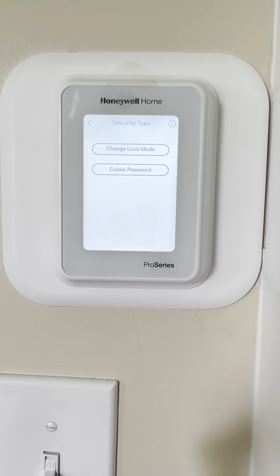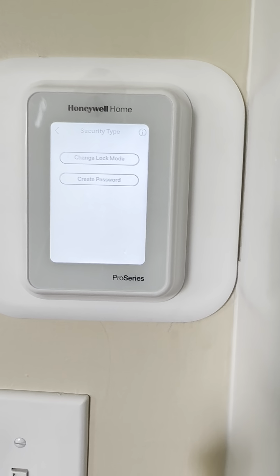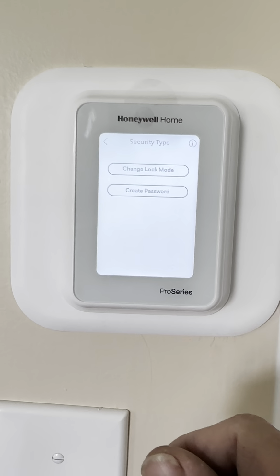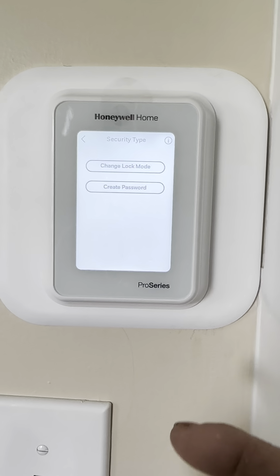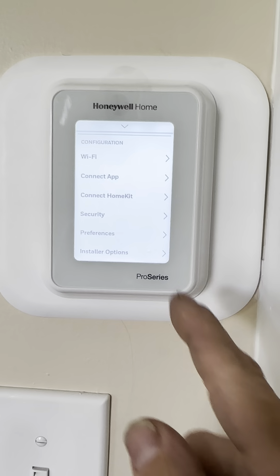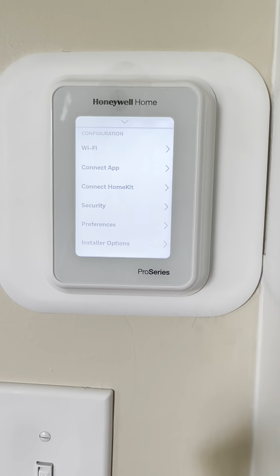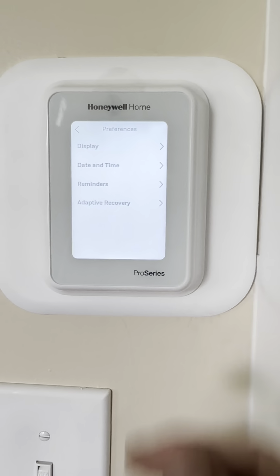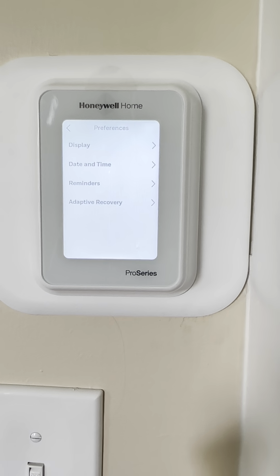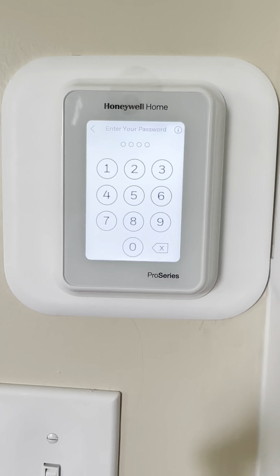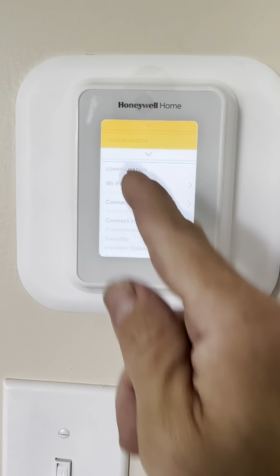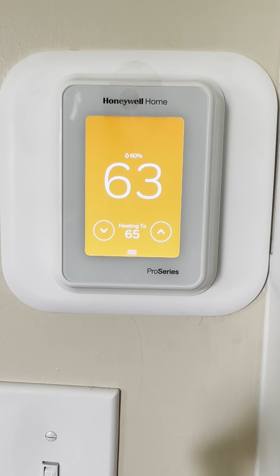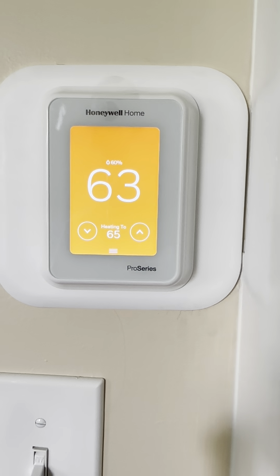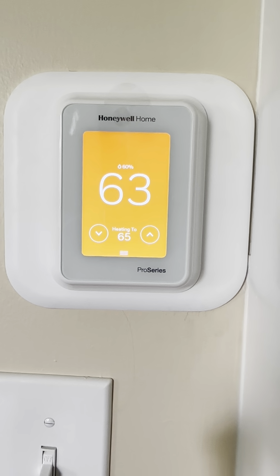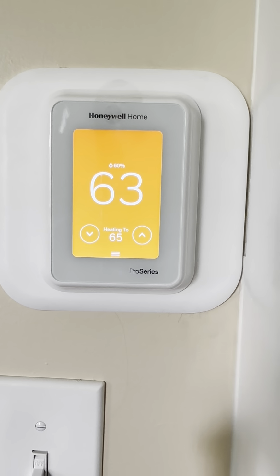Security, you can set a lock passcode for this if you have kids or something of that nature. Usually rentals and things of that sort, people like to have a passcode on there. And further down the list are kind of things that we run into. You can set the date and time and a few things in your preference screen here, but then we have our installer options at the very bottom. So at this point, we're still running in heat, so we have some airflow now. We can hear the air coming out of the vents, and we're gonna go ahead and move on down to the air handler at this point.